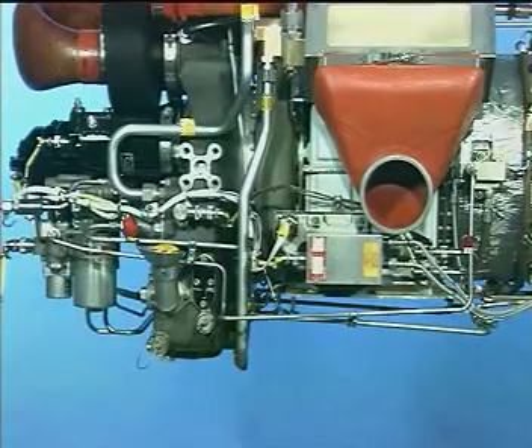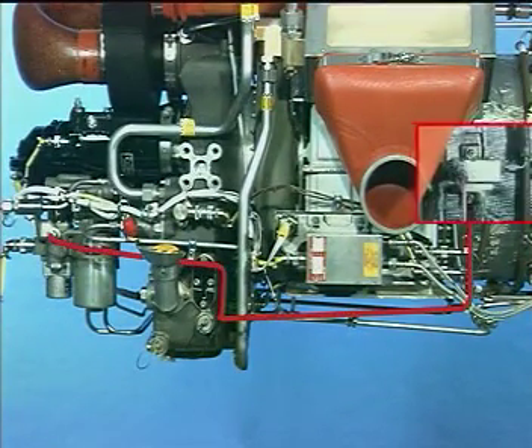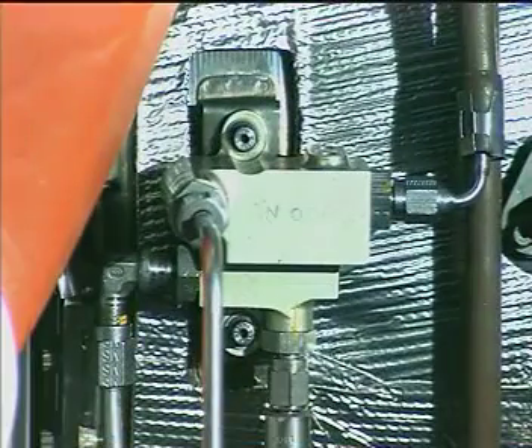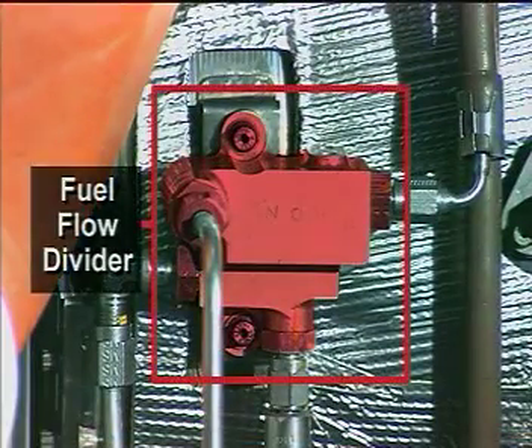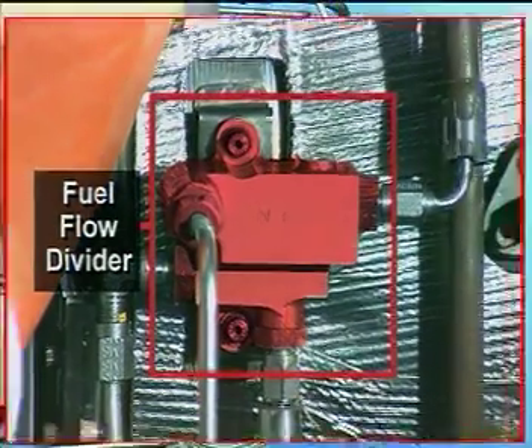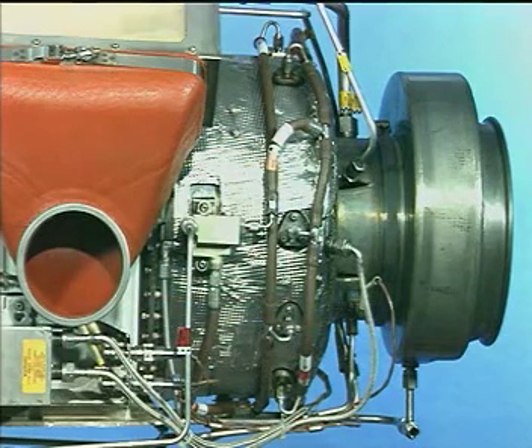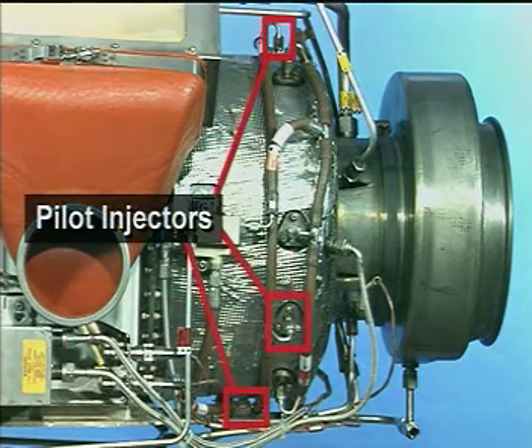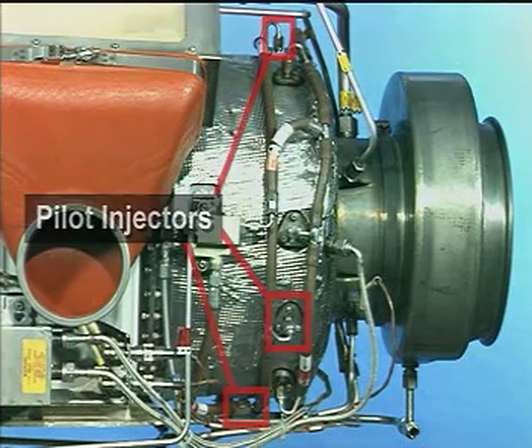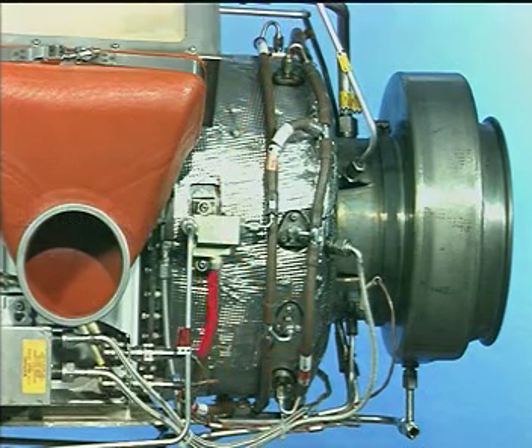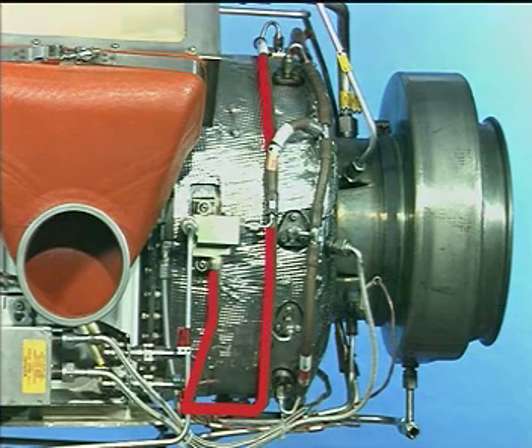When the three-way solenoid valve is opened, the metered fuel is supplied to the fuel flow divider located at the 9 o'clock position on the turbine case. The flow divider distributes the fuel to the two fuel manifolds. During the initial start sequence, fuel is supplied to the three pilot injectors through the pilot injector manifold. When the fuel pressure increases to a specific value, fuel is supplied to the 6 main fuel injectors through the main injector manifold.